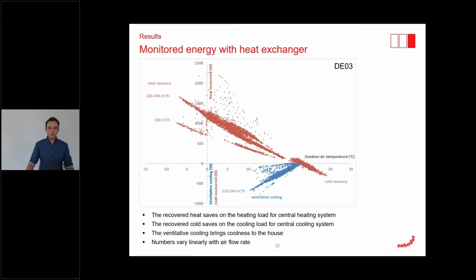So let's take a look at the monitored energy savings with the heat exchanger. Here we have on the horizontal axis the outdoor temperature, and on the vertical axis the heat recovery and the cold recovery, as well as the ventilative cooling in watts. Let's take a look at what happens in winter. Here we have the highest heat recovery rates. This is due to the bigger temperature difference. So at lower temperatures, we get more energy savings, logically. And we can also see a dependence of the heat recovery on the air volume rate. The higher the air volume rate, the higher the heat recovery.